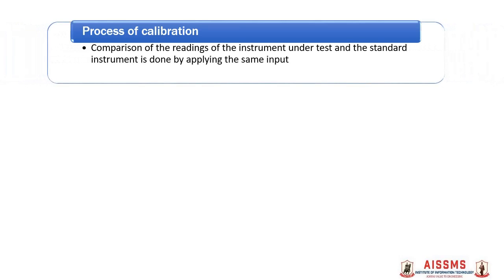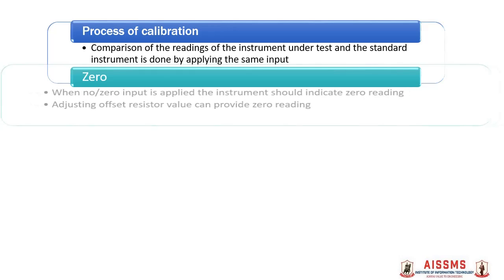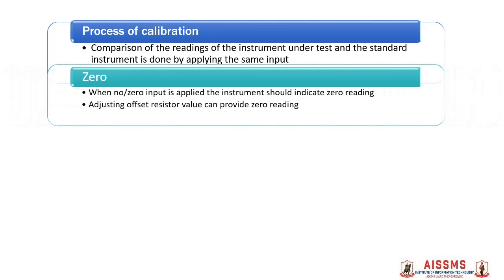Calibration is simply the comparison of the readings of the instrument under test and the standard instrument by applying the same input. When there is zero input applied to the instrument, the instrument under test should indicate zero reading. If it is not showing the zero reading, we need to adjust the offset resistor value to get the zero reading. This is called zero adjustment.